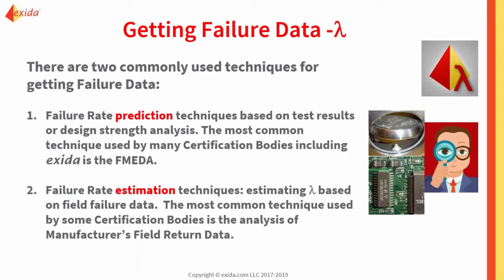One of the most common ways to predict failure rates is an FMEDA, or failure mode effect and diagnostic analysis. And that's what we here at Exida use to predict failure rates. We're going to look at what that is and how we do that coming up. The second way of obtaining failure rates is through an estimation technique. And estimating failure rates is usually done by looking at historical data like field return data, end user field studies, that type of information. But the most common technique is the manufacturer field return data study.